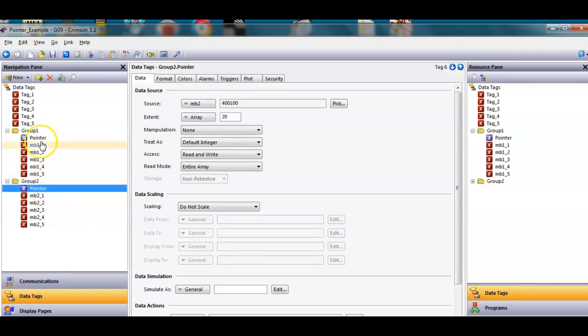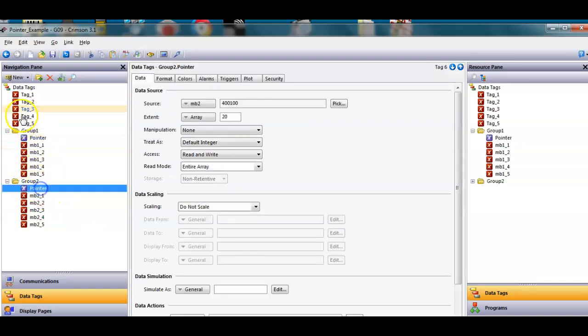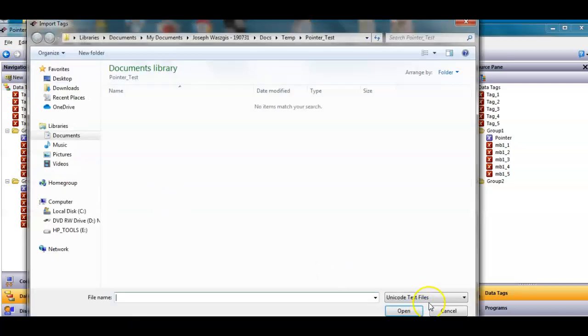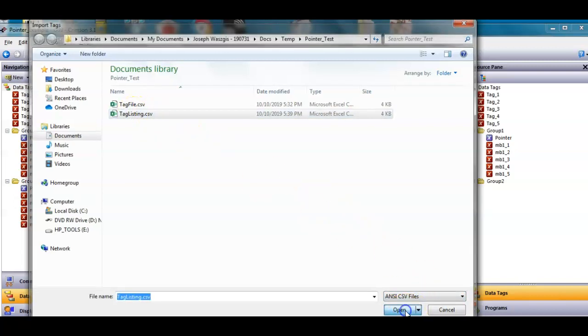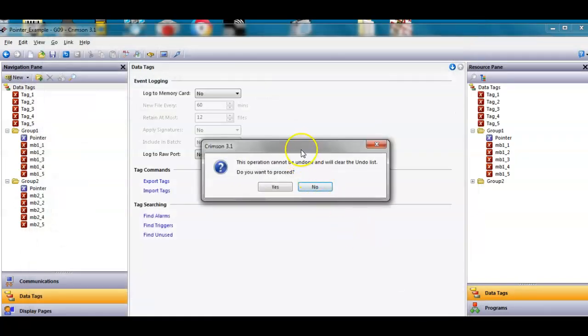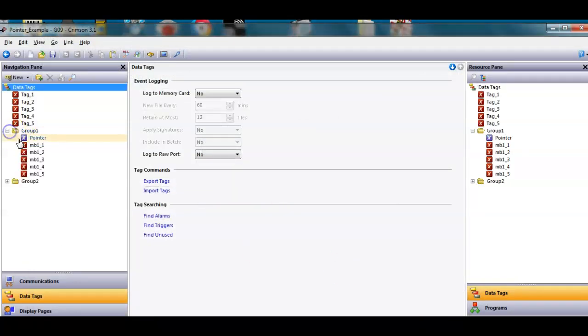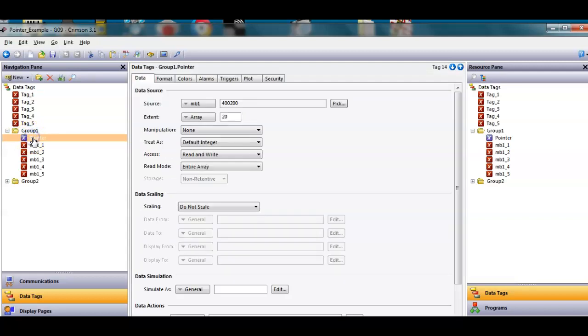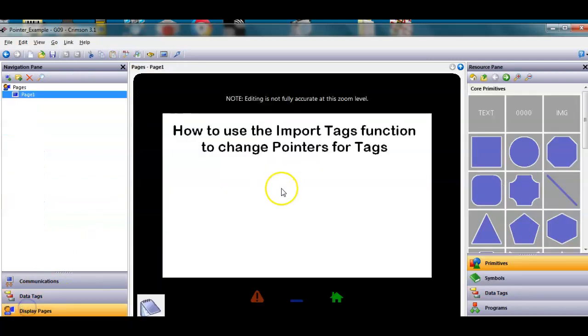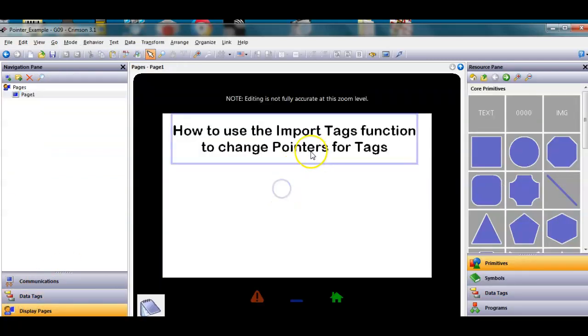I want to see if these numbers, these pointers change. So I'll click data tags on top, click the import tag button. Make sure I'm looking for an ANSI CSV. I'm going to click the tag listing file right here, click open. It's going to bark at you, cannot be undone, say yes, proceed. It should have imported. Let's check our work. If we go over here, this one's now looking at 200 right there, and this one here should be looking at 1234. It is. So that's an easy way for you to change the pointers.